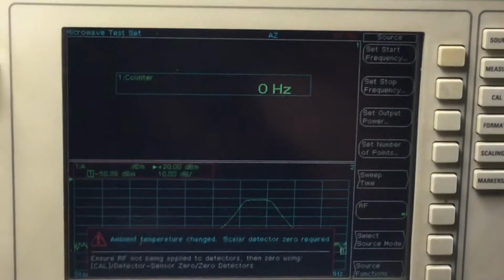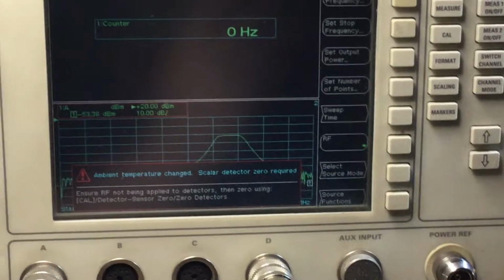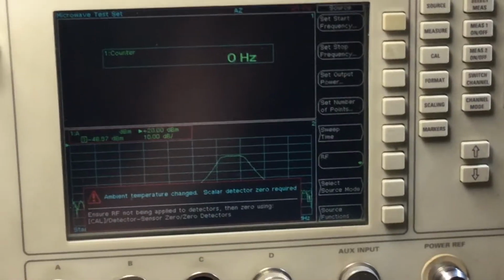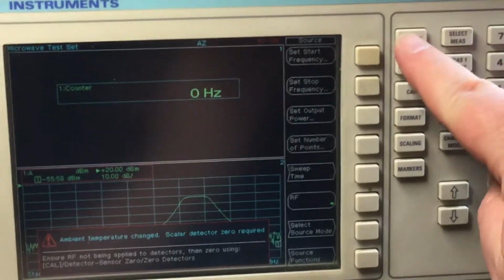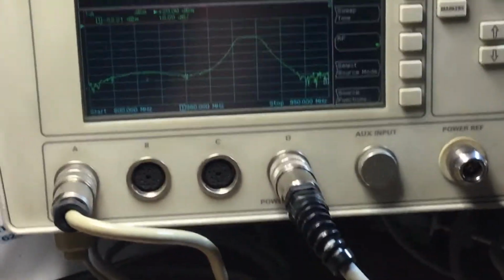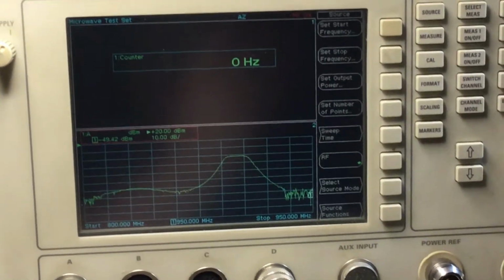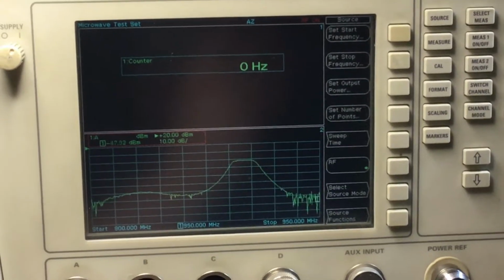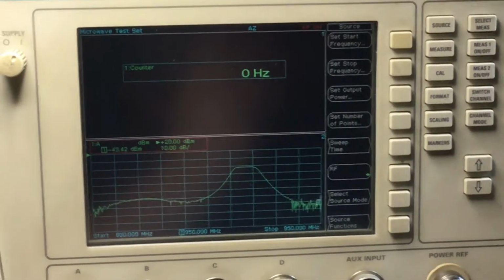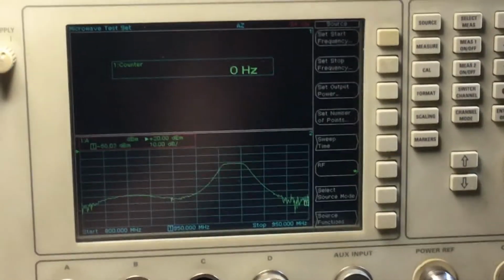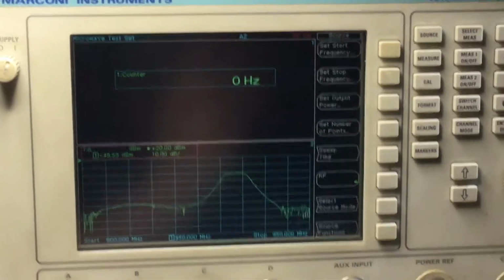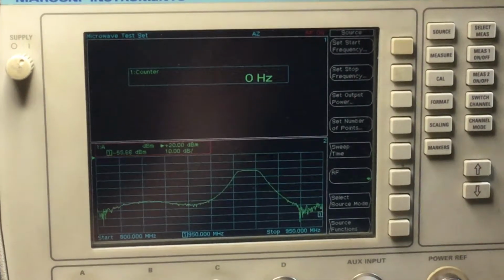At the top here I've got the frequency counter if we were to use that, but this is the main measurement. Another thing about these test sets - they're so sensitive, and used in laboratory or research applications, that as the ambient temperature in the room changes, or even handling the sensors with your hands, the heat from your hands affects its accuracy. That gives you an idea of how accurate this instrument really is, where air temperature can actually affect the measurement. That's serious stuff - it shows you what we're dealing with here.